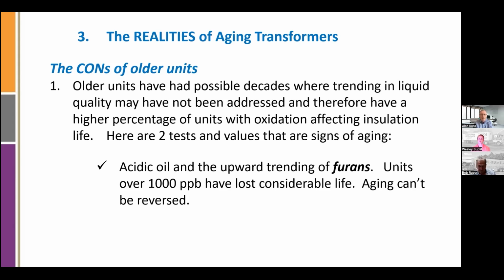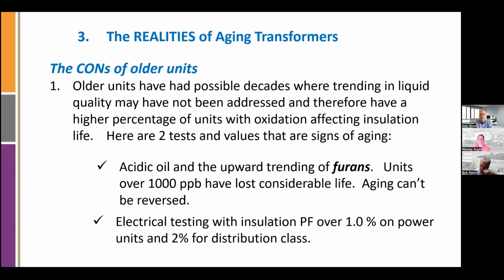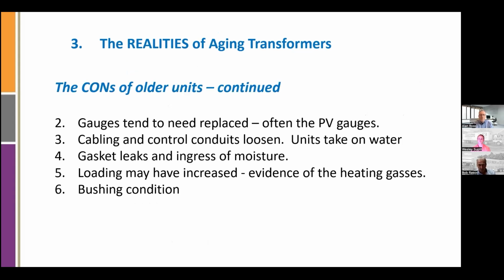That's part of our content here today. Electrical testing, another great thing to do to transformers. And NFPA 70B says 3 to 5 years. Insulation power factors are a good indicator of the condition of the insulation system. That includes the liquid and the paper. These are some of the things that we're always chasing around to improve the transformers in the field service world.